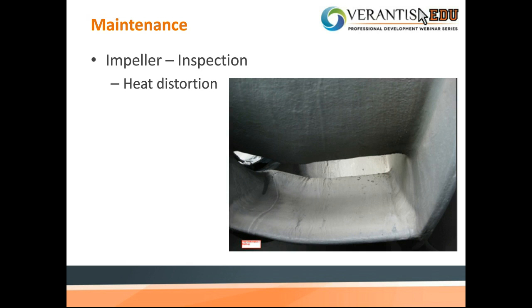This also can go back to monitoring. If a damper is closed and the fan is operating, that heat has nowhere to go. So what inevitably happens is that there's a heat buildup within the housing, and it can be destructive in nature if not caught in time. Yeah, as Craig said, if you see an impeller with this kind of wrinkling and cracking, or bowing of the blades where they should be perfectly straight, do not run the fan. You're looking for a catastrophic failure to happen.